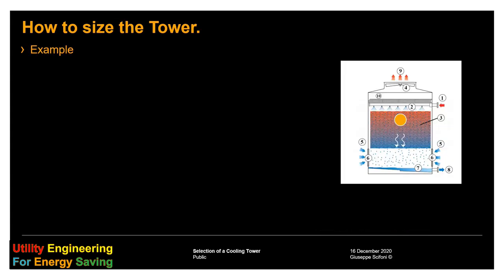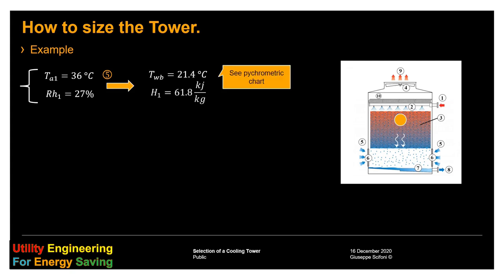Starting from the ambient condition, we know the temperature of the air and its relative humidity. On the right side, we have a picture with the cooling tower and position number five is the entry of the air. By means of the psychrometric chart, we can determine the wet bulb temperature and the corresponding enthalpy, H1.